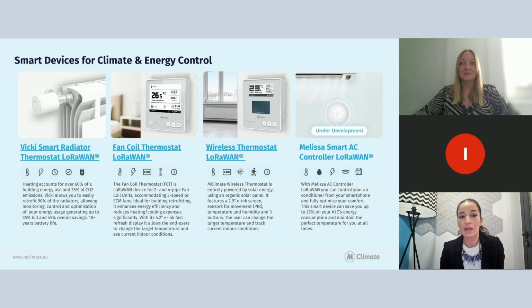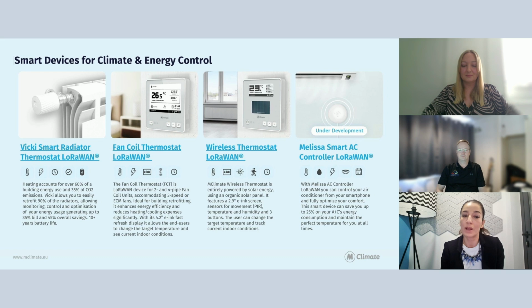Fan coils are also quite interesting. They're mostly typical for class A buildings, offices, and a lot of hotels. But again, most of them are quite obsolete and old, and building management systems date back 10, 20 years. So really, taking over the fan coil allows us to efficiently control room by room and get the relevant data all in one system.